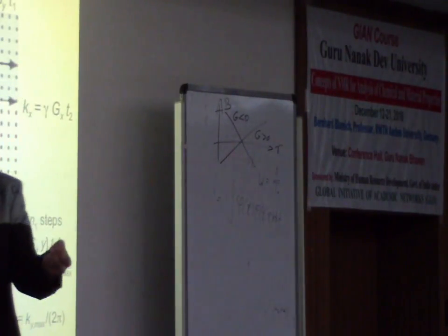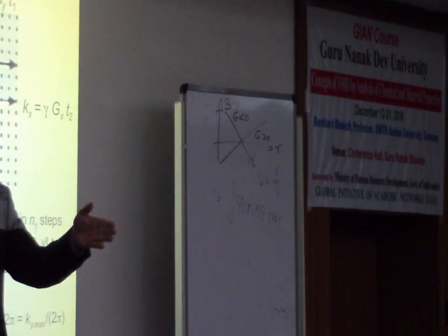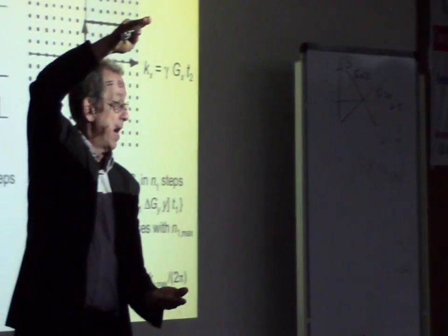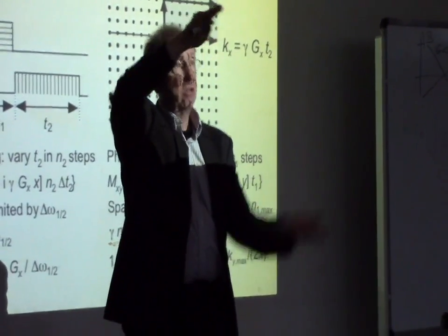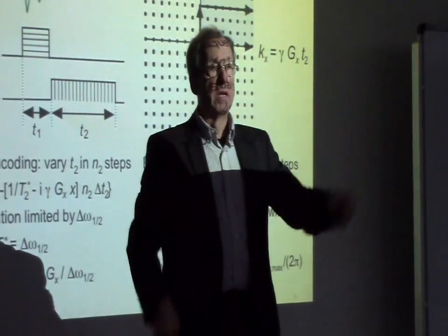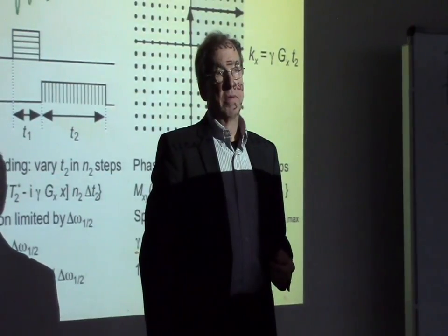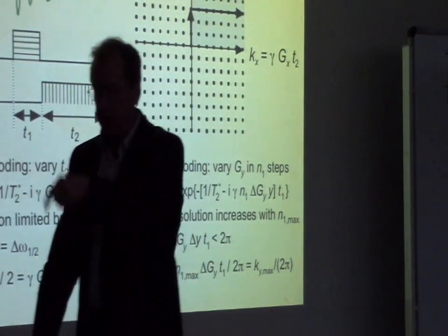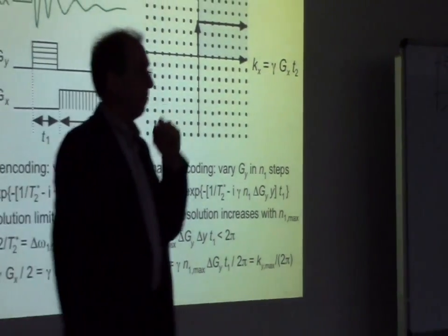And this way you manipulate the gradient integrals, that is, you manipulate K. And you have in fact three sets of coils, one in X direction, one in Y direction, and one in Z direction. So you are able to do three directions of gradients, and you can switch gradients positive, negative, and off. Let's do the other slide later on. We have other questions.